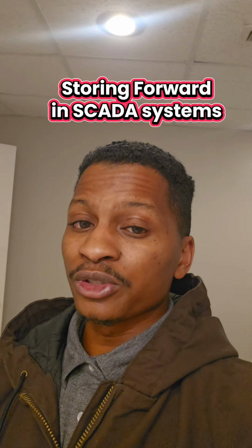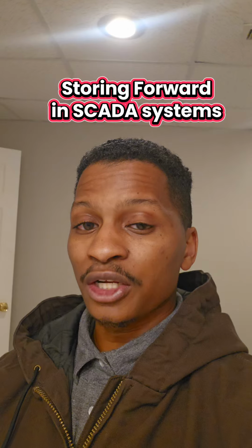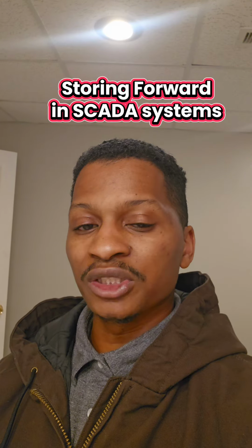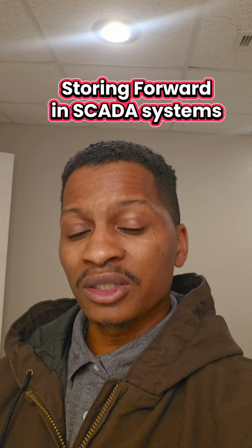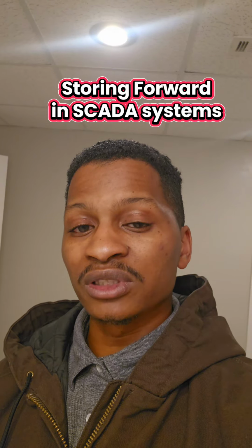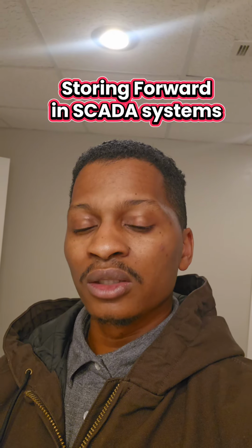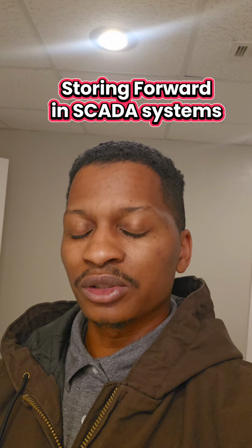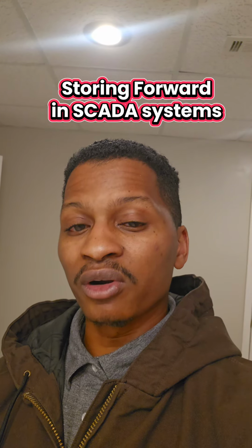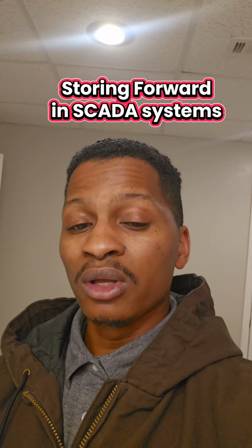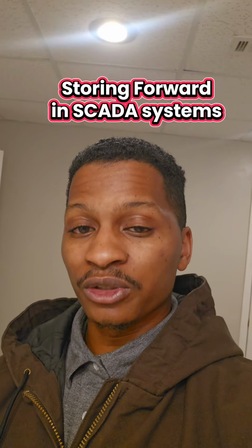But let's say your SCADA system loses connection to the database, maybe it's talking over TCP or something, and you lose that connection. Well, what happens to all that data you're logging? So you're going to have something called store and forward. It kind of sounds like what it sounds like. Your SCADA system is still going to collect all that data and put it into a buffer or a disk while that database connection is faulted or disconnected.